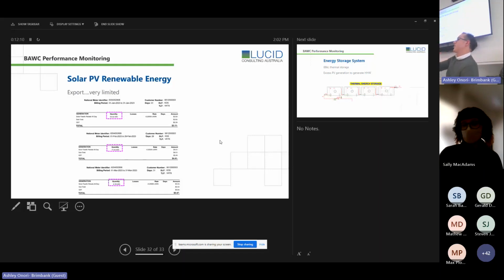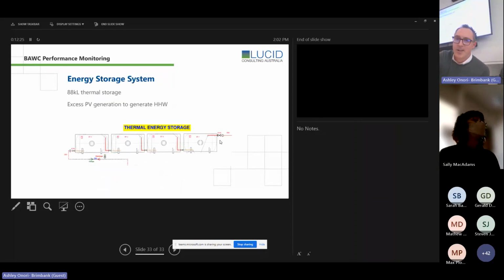We've got the compounding impact of rising electricity input because the energy demand of the facility is increasing, but you're getting less out of your PV system - so that's next to no export. The issue of export is a bit interesting on this project, because the fundamental basis for the thermal energy storage was that with a very large PV system, you're going to have lots of export. Instead of exporting, you want to run the heat pumps to charge the thermal energy storage, so instead of just rejecting energy to the grid for very low cost, you're using it to generate thermal energy to store and then use in the pool.